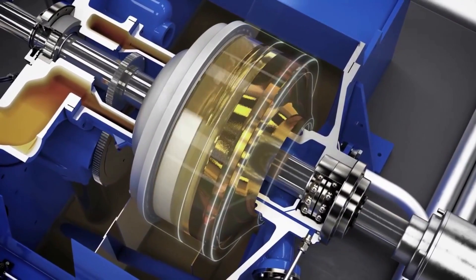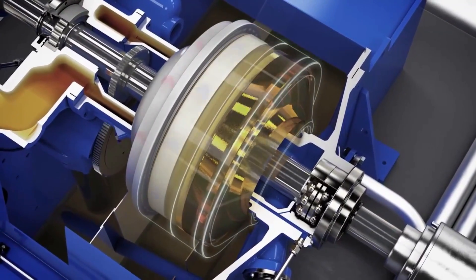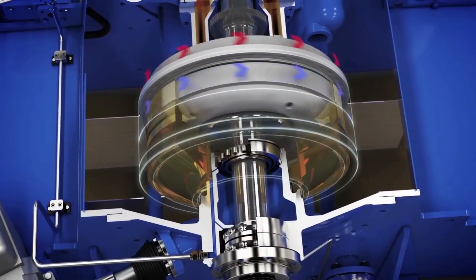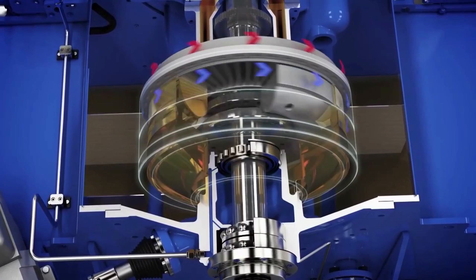The pump speed is controlled by the oil fill level in the coupling. This is done using a scoop tube that extends or retracts in order to change the fill level.